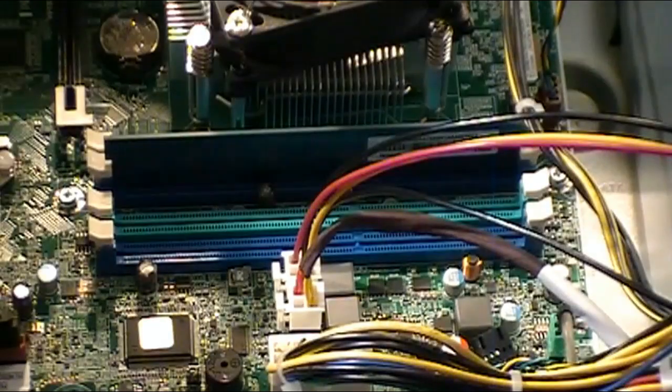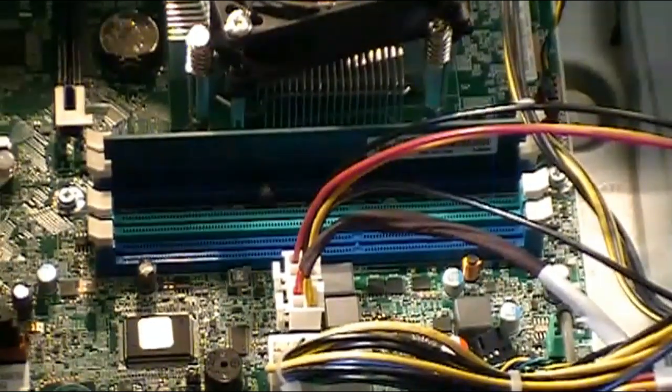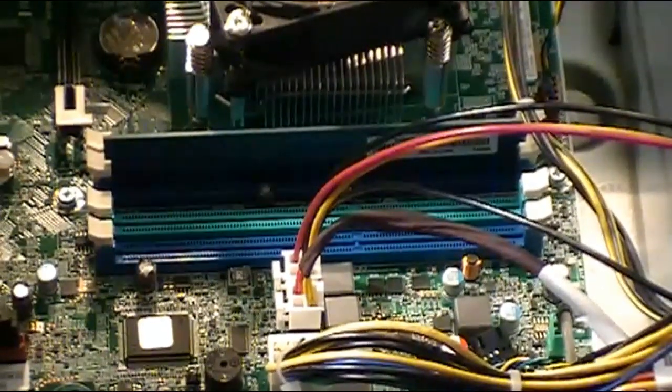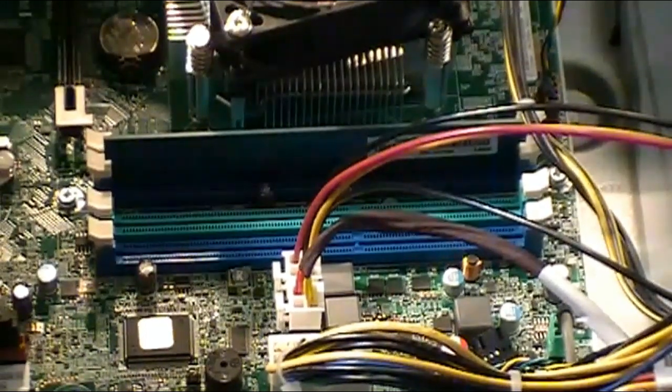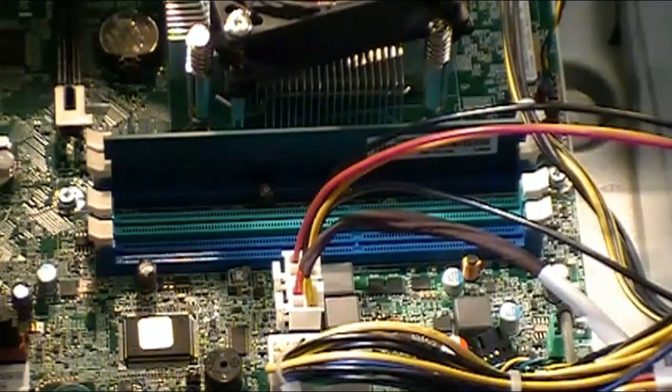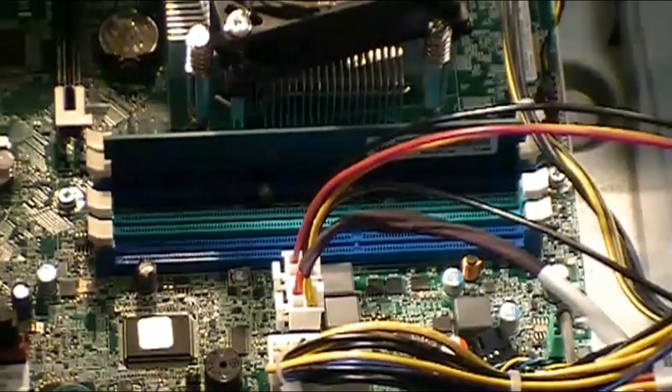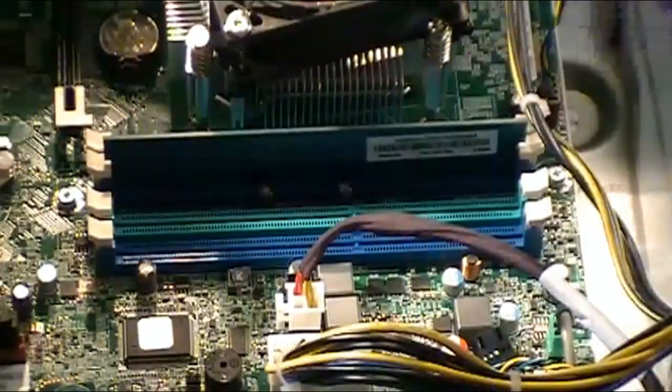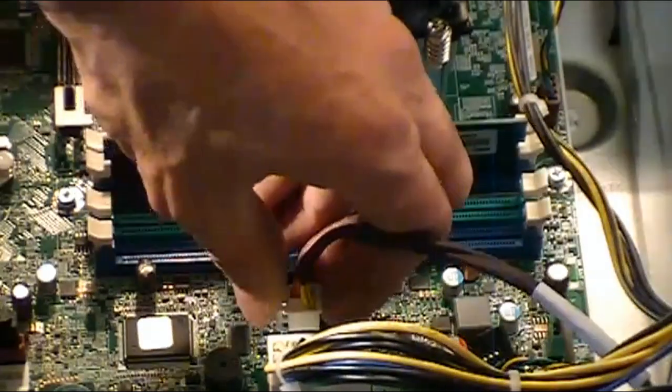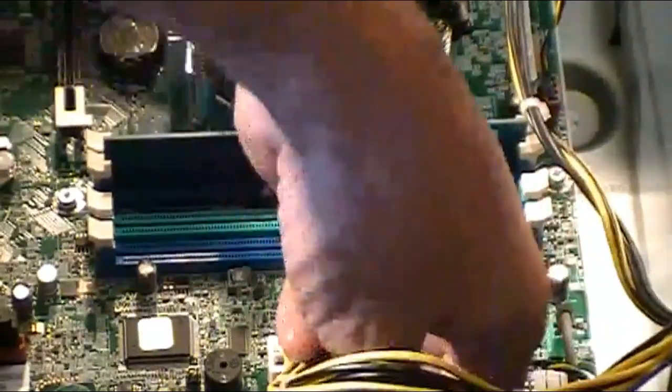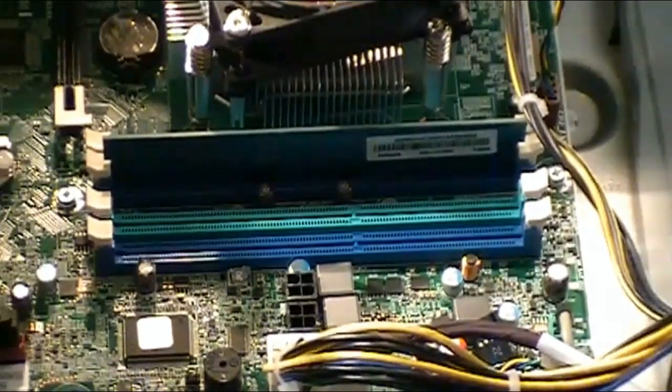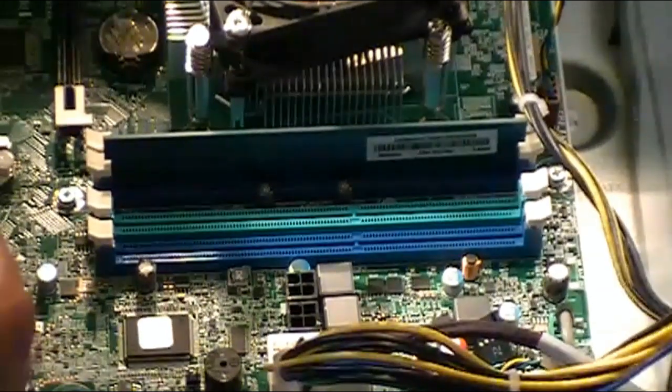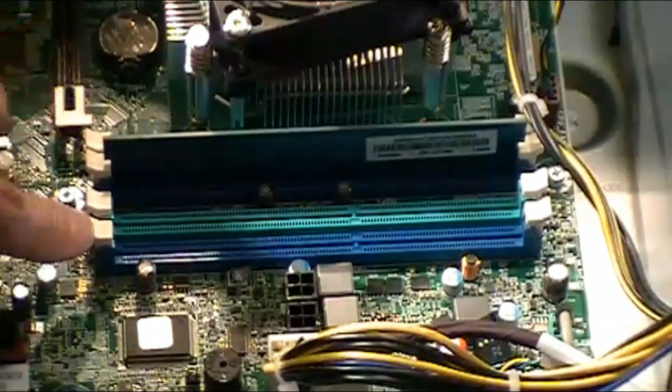RAM installation of these, just like any other PC, you want to maintain ground to your device. You can use a wrist strap if you'd like. Or you just need to make sure that your arm, wrist, elbow, something is touching the frame of the server while you're working on this. You do not want a static charge going through any of these chips while you're working on them. I'm going to disconnect a couple of these power cables just to get them out of the way so you can see easier what I'm doing in here. So I'm grounded to the case right now, outside the frame of the camera. And like I noted before, there's a blue and a green slot.